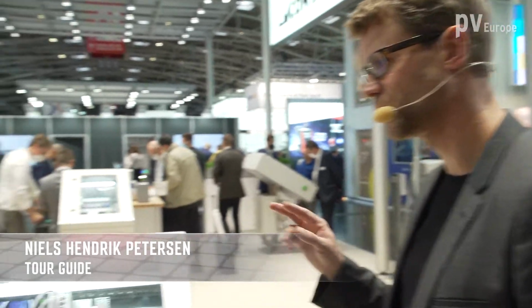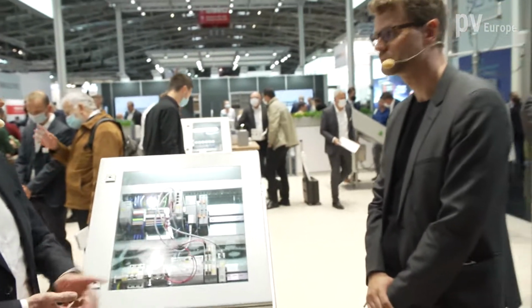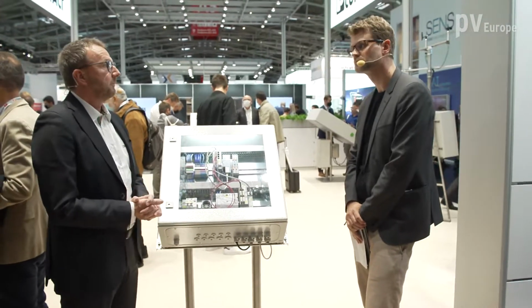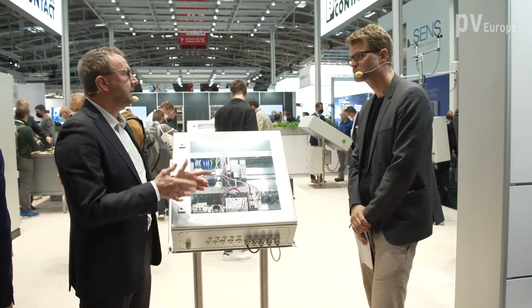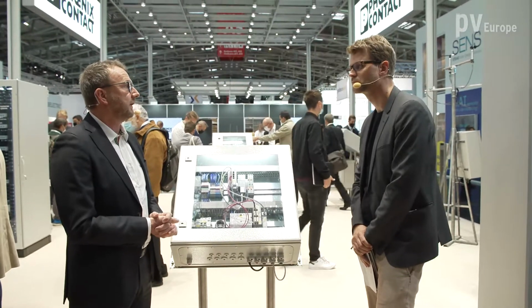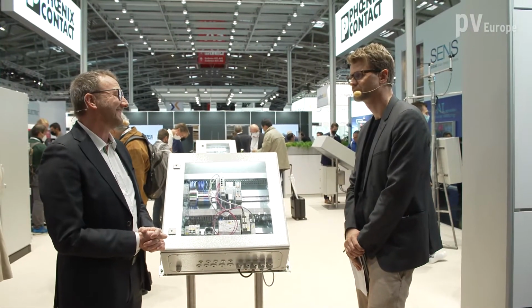Is this limited to 2 plants, or can you add 10 or more? For the pre-setup, it's just for 2 different energy generators, but it can enhance to several, because you just copy one instance to the next one. That means you can handle 5 to 10 if you like, depending on the performance of the controller. It's independent of how many different energy generators you connect together at one grid connection point.